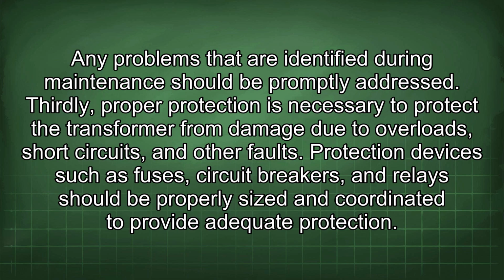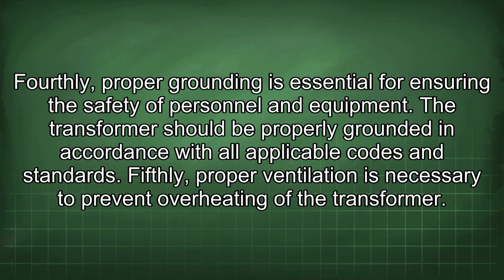Thirdly, proper protection is necessary to protect the transformer from damage due to overloads, short circuits, and other faults. Protection devices such as fuses, circuit breakers, and relays should be properly sized and coordinated to provide adequate protection. Fourthly, proper grounding is essential for ensuring the safety of personnel and equipment. The transformer should be properly grounded in accordance with all applicable codes and standards.